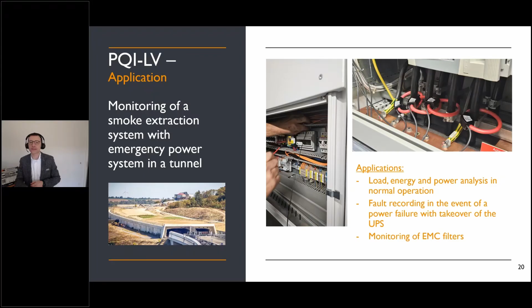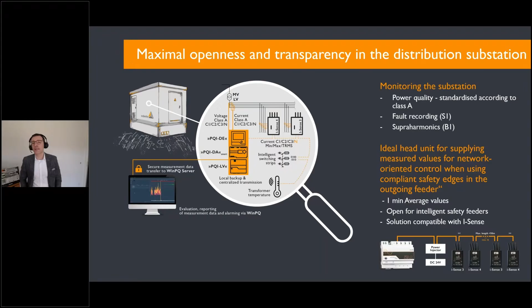But in the distribution substation, you can use the device as well. Again there are 3 applications: power quality, fault recording, and supraharmonic measurement, as well as an ideal head for supplying measured values for grid-orientated control over our Modbus master technology. Therefore, we also provide a solution with the iSense technology. We can record up to 16 feeders in case of currents, and the installation is also very easy.